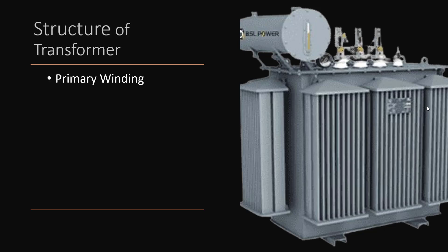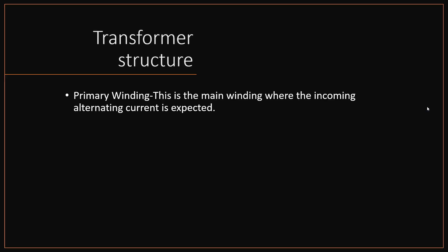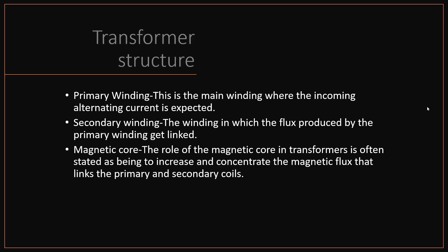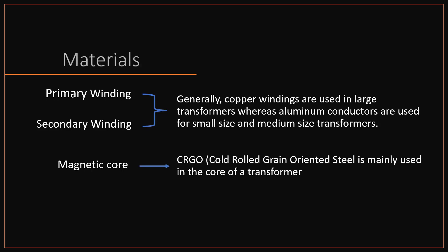Every transformer has three parts: primary winding, secondary winding, and magnetic core. Primary winding is the main winding where the incoming alternating current is received — the AC supply from a generator or power station comes into the primary winding. Secondary winding is the output side. The function of the magnetic core is to increase or concentrate the magnetic flux that links the primary and secondary coils. The magnetic core is an iron core. For large transformers, primary winding is made of copper; for small and medium-sized transformers it may be aluminum. The commonly used core material is CRGO — cold-rolled grain-oriented steel.